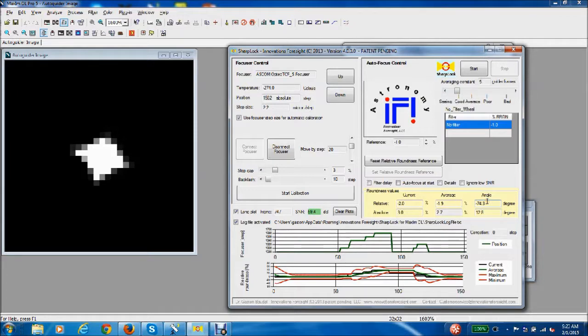See the angle, roughly 74 degrees, and now you can start the autofocus operation. You are done with the calibration. And your system will start to track any change in focus relative to the reference roundness you just set.